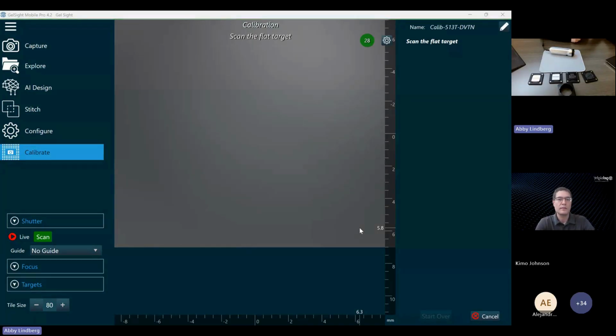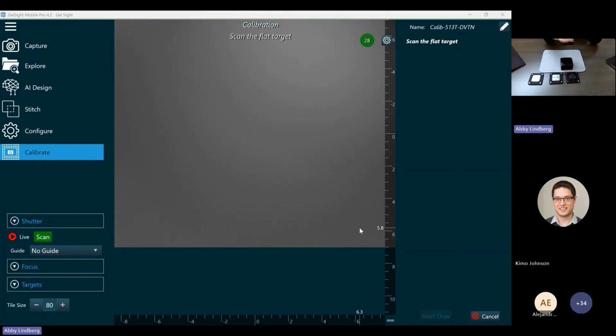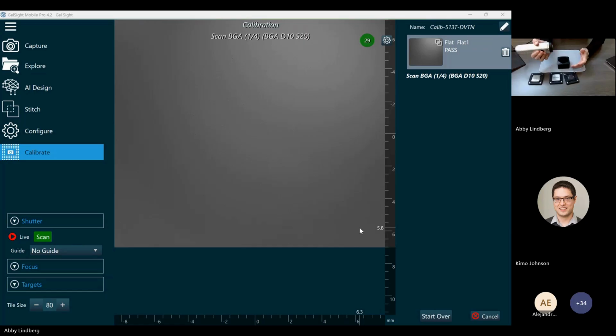So the first one says scan the flat target. I'm going to take our flat target, and I'm also going to take our alignment fixture. So this just snaps on to the front of all of our targets like that to help us align to that target with our system. So I've got our Series 2 here, and I'm just going to press it down through my alignment fixture onto the surface of that target. And the goal for this is really to just make contact in all 4 corners. And I click the button to take the scan. And as Kimo just described, we're doing this to look at the fall off of the illumination system around the edges.